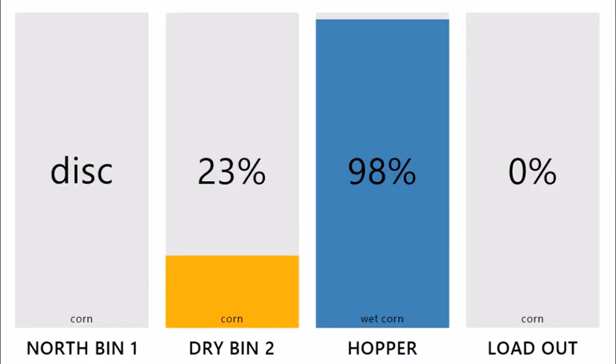The most common issue you may see with your system will be the disconnected error. This error is typically due to a problem with the connection to the sensor plugged into the associated port, and it can usually be fixed simply by checking the connection between the cable and the monitor, or between the sensor cable and the extension cable. Make sure that all connectors are fully seated, are not stripped, and are tightly screwed in with no pins bent or damaged. If the connections look secure, check the cables and sensor for damage. We are now finished setting up your new MTEC FullVIEW bin level monitoring screen.